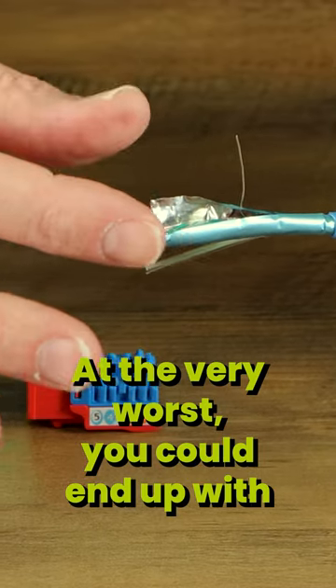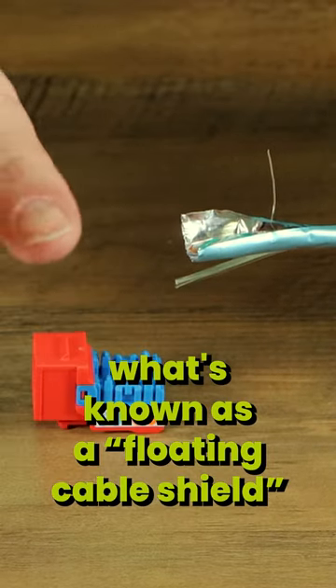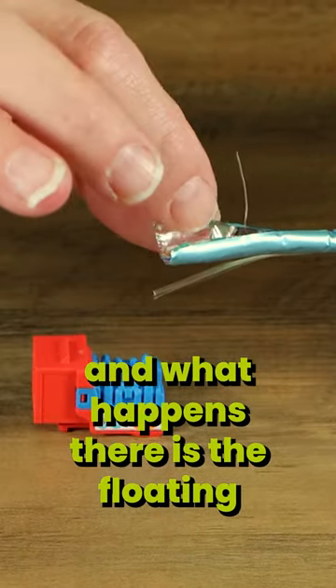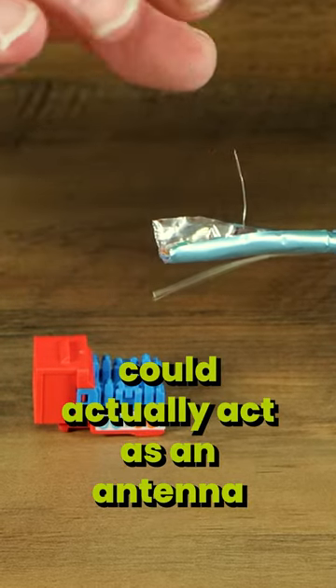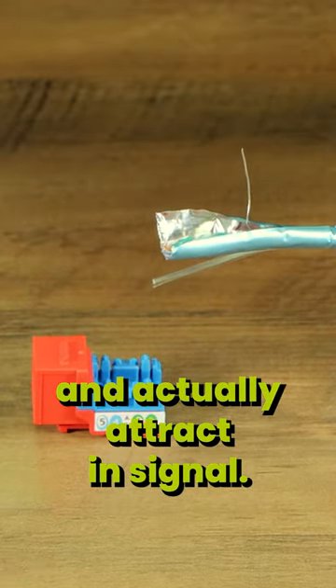At the very worst, you could end up with what's known as a floating cable shield. And what happens there is the floating cable shield could actually act as an antenna and actually attract in signal.